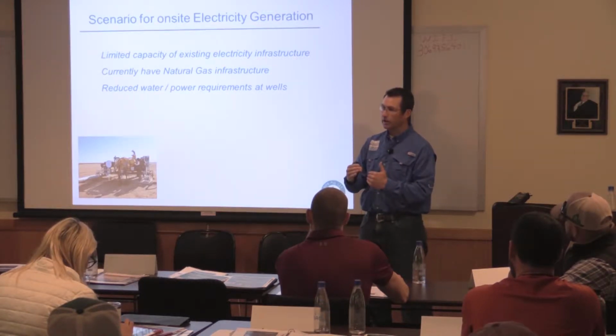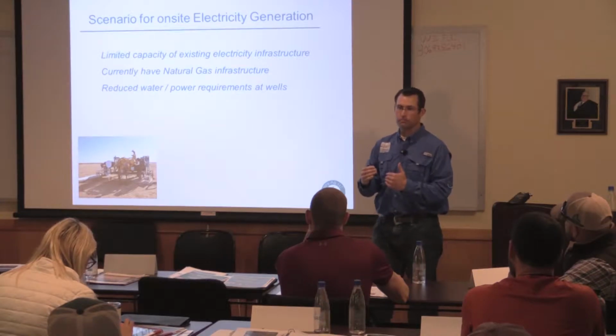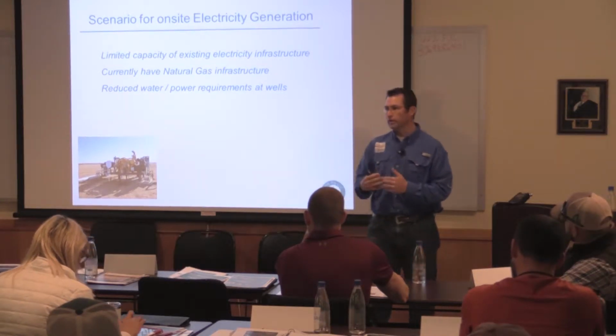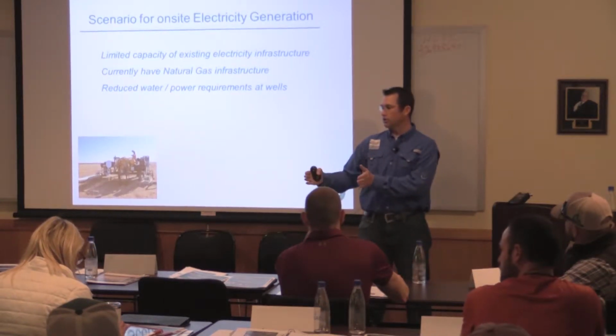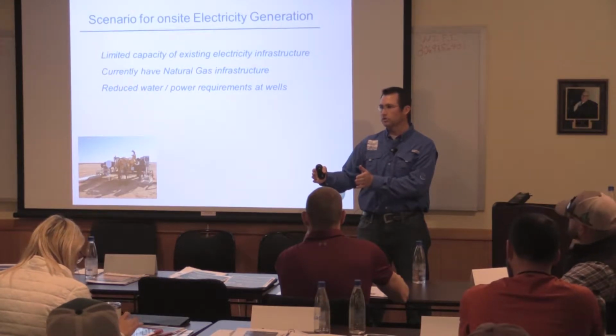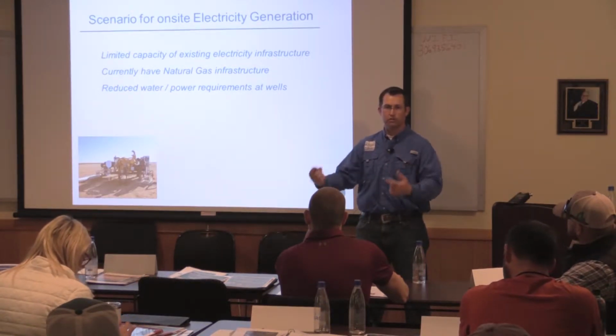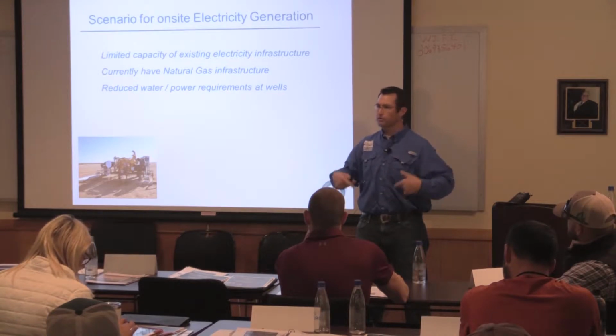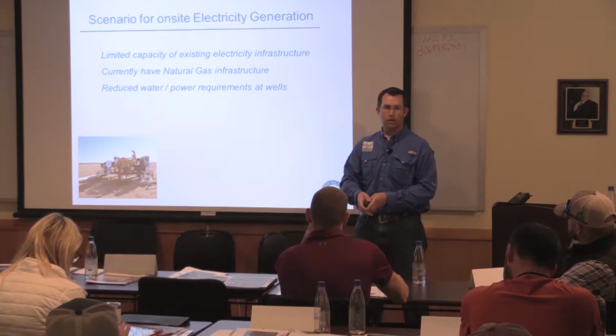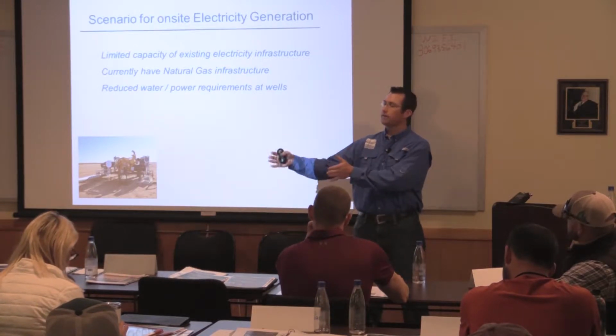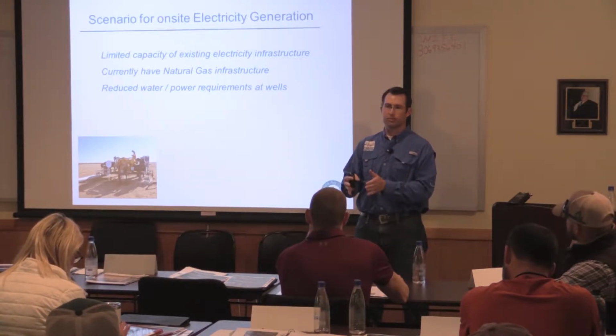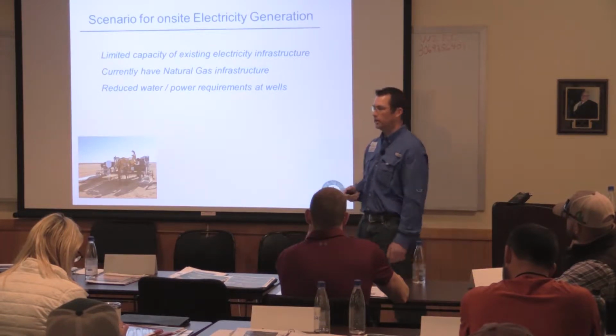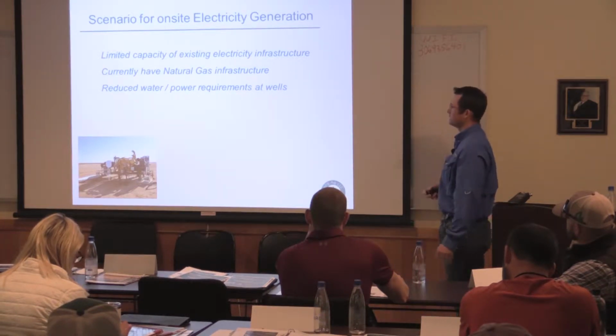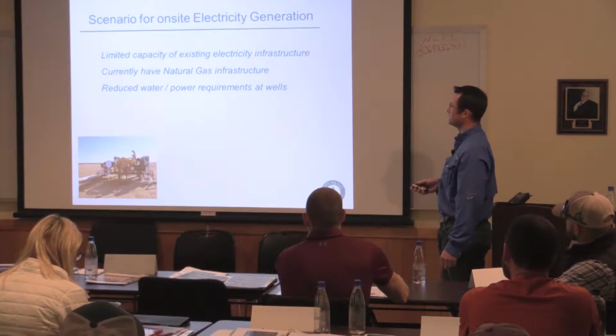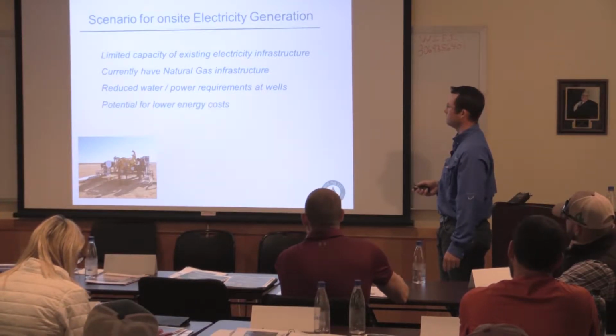If you're operating at a lower loading, the mathematics of it is your internal losses from heat, your thermal losses from turning that much steel—you're going to be turning that whether you're loaded or not. So your efficiency of the power you're producing goes down. In cases where you go from 500 gallons per minute to 250 gallons per minute, say, and you want to look at a smaller pumping plant, this is another criteria that helps make the decision for converting to gensets.